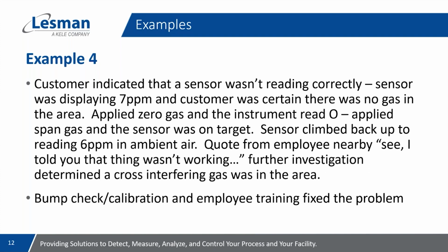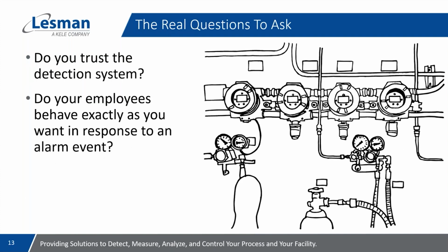So we've discussed terms and shared examples of what to avoid, but the open question is still, what should my maintenance interval be on my gas detection system? I'd suggest a real question to ask is, does your team and do you trust the information your gas detection is providing? Most importantly, will the employee behaviors during an alarm condition meet your expectation? Do they move and react in the way they're supposed to, or do they look around confused about what the horn means? This has to be the starting point.